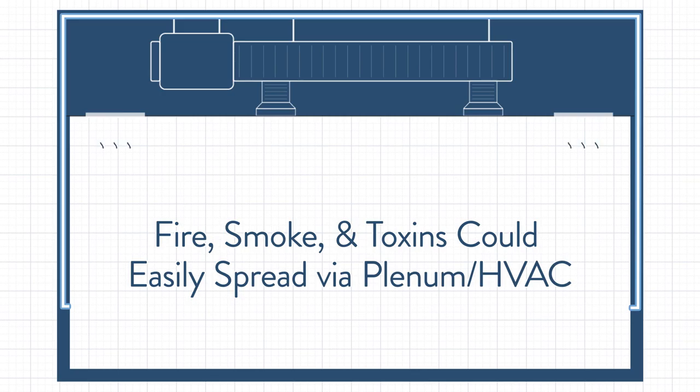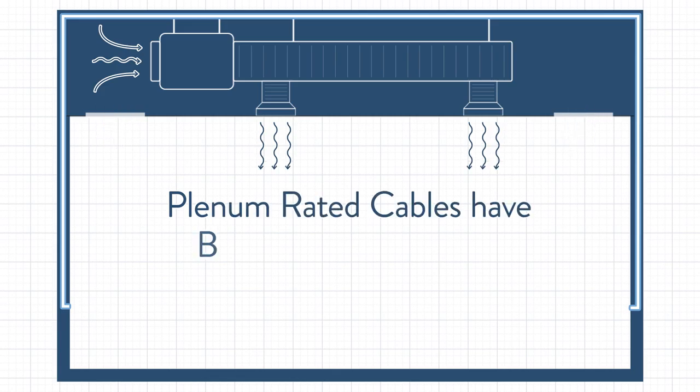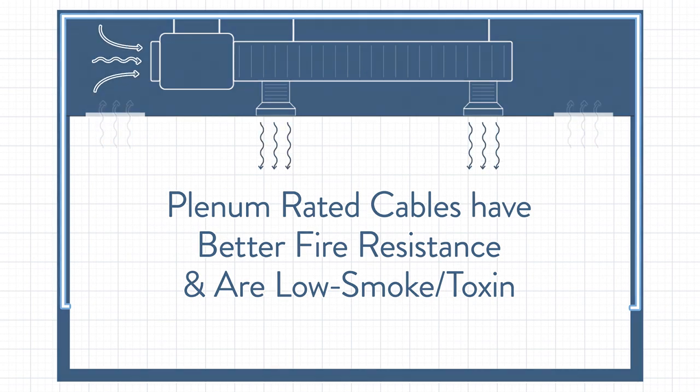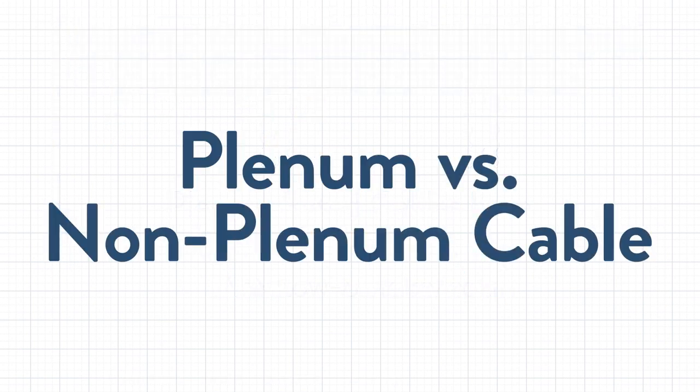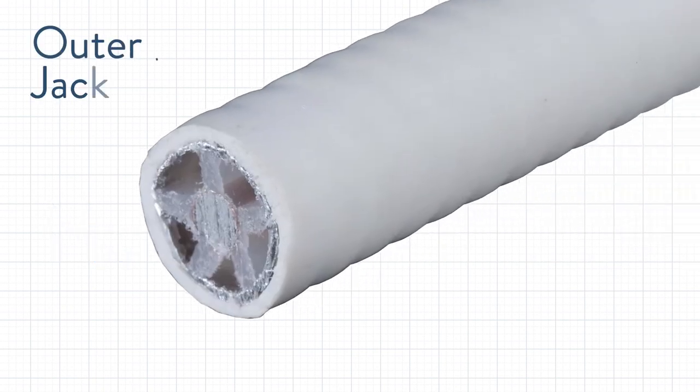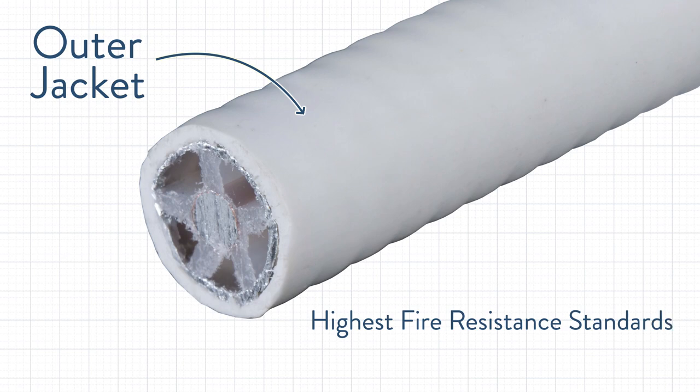For these reasons, plenum spaces require cables that are plenum rated, which means they meet higher standards like being more resistant to fire and producing less smoke and toxins in the event of a fire. Technically, any cable could be made into a plenum rated cable. The key difference is that plenum cables have a superior outer jacket or insulation. This outer jacket holds up to the highest fire resistance standards while also producing the least amount of smoke or toxins in the event of a fire.